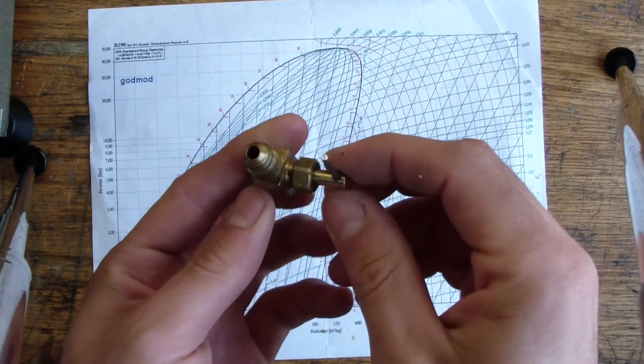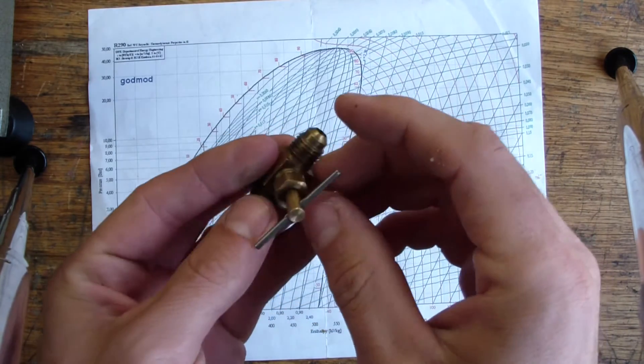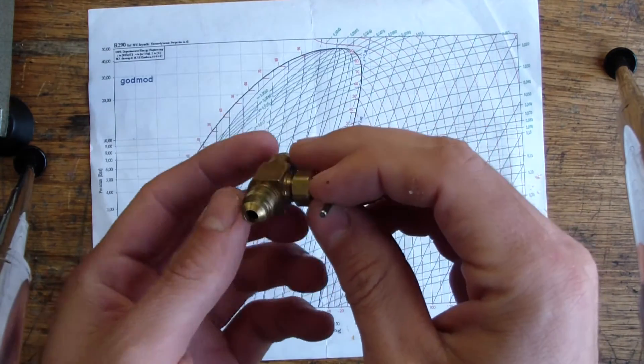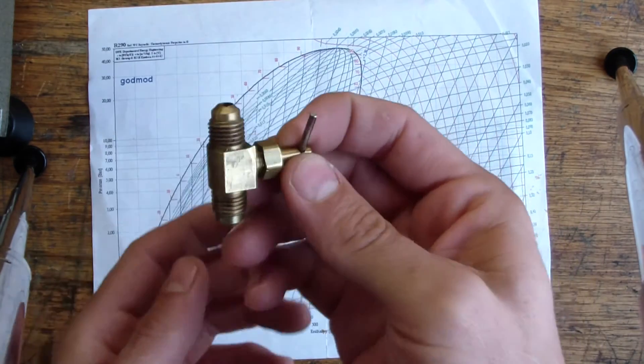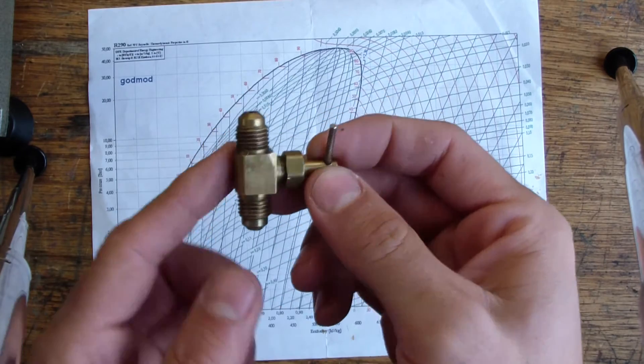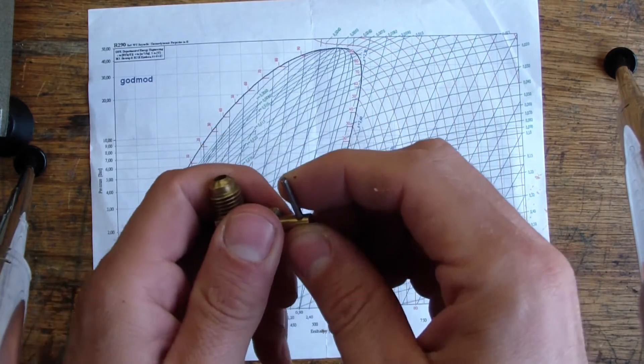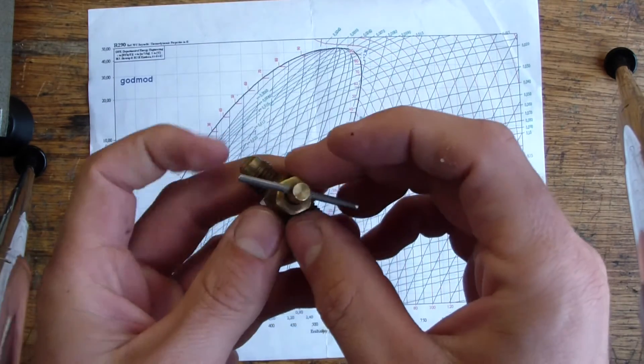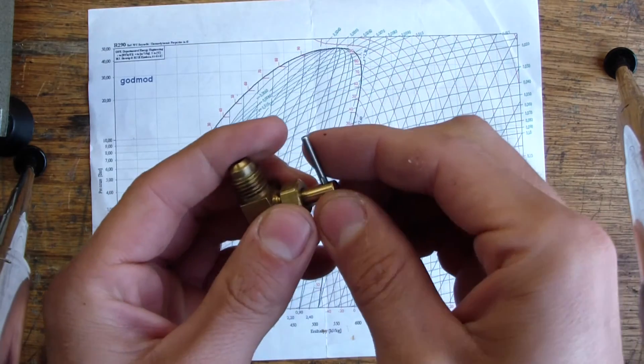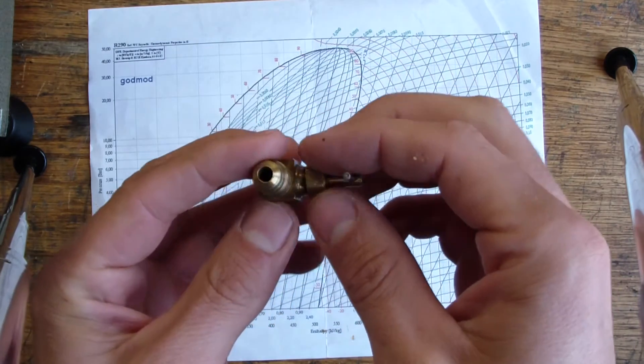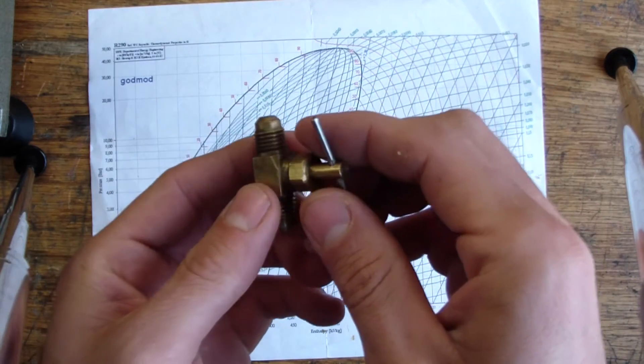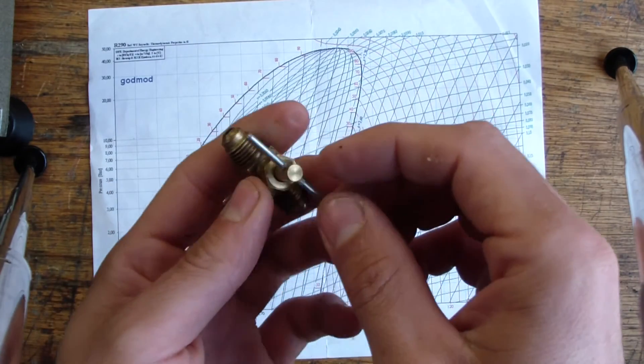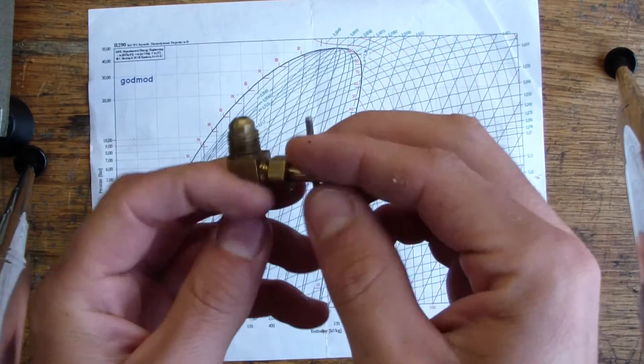And too loose, obviously it's going to leak. These things can be a problem if you're going to use one for kind of long term. Especially if your evaporator temperatures are very low and this thing frost over, it will frost over. If you try to adjust it while it's extremely cold, you could have issues with that valve packing in there leaking on you because you're going to have some contraction of the valve packing. It's not going to make a proper seal and you're going to start getting refrigerants leaking out of there, which is no good.